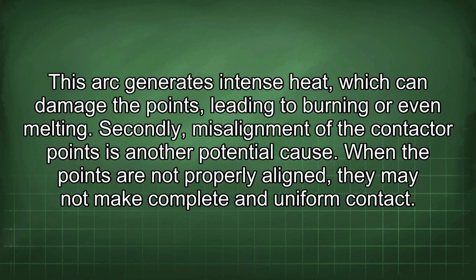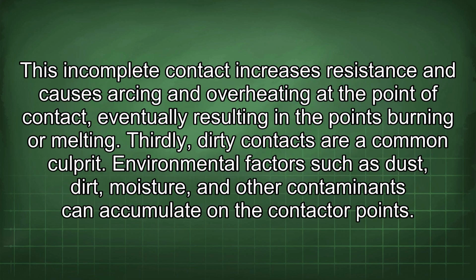Secondly, misalignment of the contactor points is another potential cause. When the points are not properly aligned, they may not make complete and uniform contact. This incomplete contact increases resistance and causes arcing and overheating at the point of contact, eventually resulting in the points burning or melting. Thirdly, dirty contacts are a common culprit.